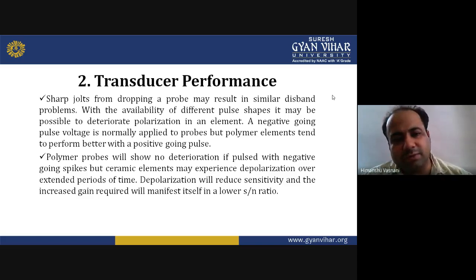A negative going pulse voltage is normally applied to probes, but polymer elements tend to perform better with a positive going pulse. The polymer probes will show no deterioration if pulsed with negative going spikes. But ceramic elements may experience depolarization over an extended period of time. Depolarization will reduce sensitivity, and the increased gain required will manifest itself in a lower signal-to-noise ratio.